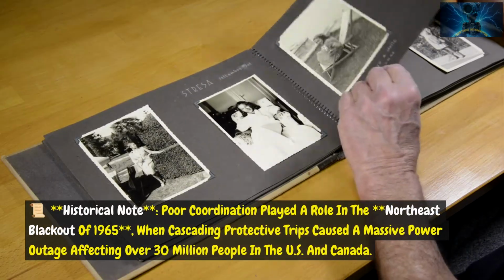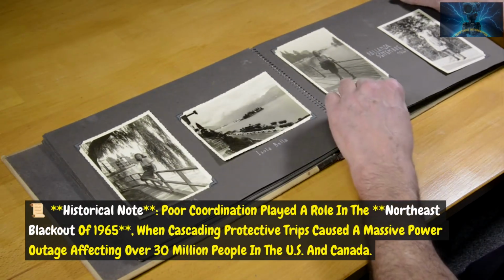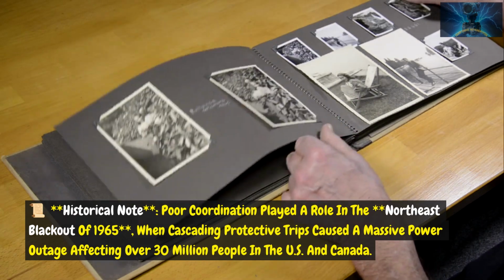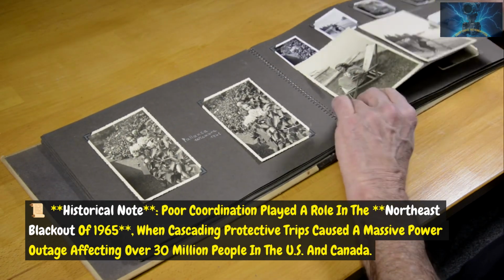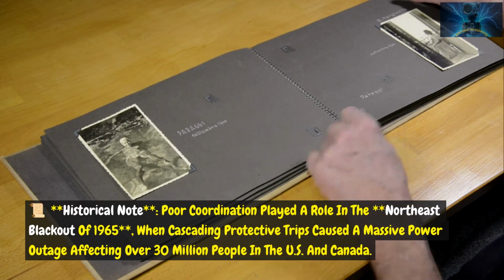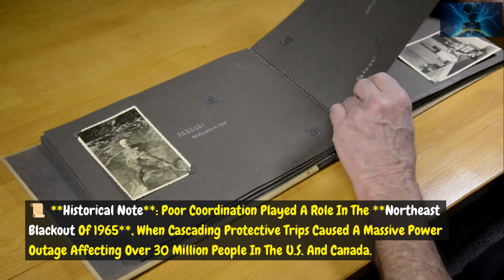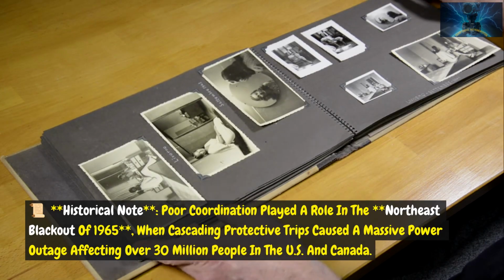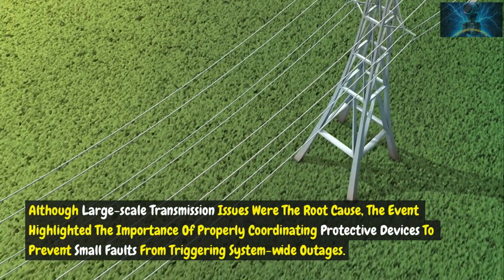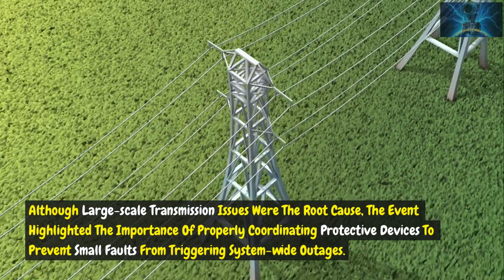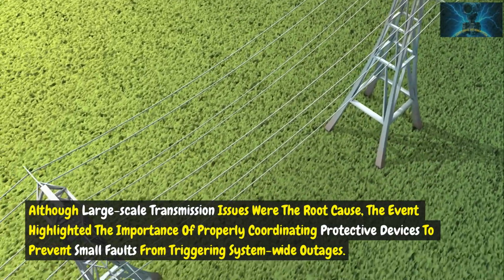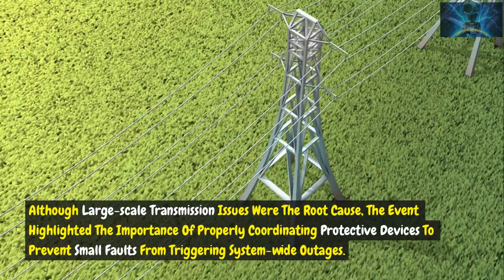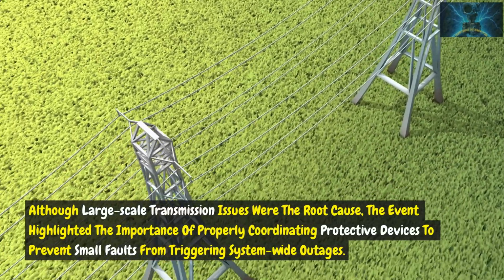Historical note: poor coordination played a role in the Northeast Blackout of 1965, when cascading protective trips caused a massive power outage, affecting over 30 million people in the US and Canada. Although large-scale transmission issues were the root cause, the event highlighted the importance of properly coordinating protective devices to prevent small faults from triggering system-wide outages.